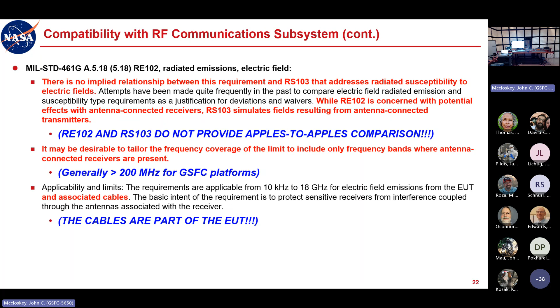It basically replaces these LISNs with a capacitor network. Actually, I'm getting ahead of myself. We'll be talking about that here presently. But this is very similar to the diagram in the mil standard, and it just defines a specific configuration for interconnecting cables. So the interconnecting cables are part of the equipment under test because common mode energy in the EUT can couple to cables, most likely will, and the cables in the frequency range where they're a significant fraction of a wavelength, generally like tens of megahertz to hundreds of megahertz, they're going to be your most efficient radiator, right?